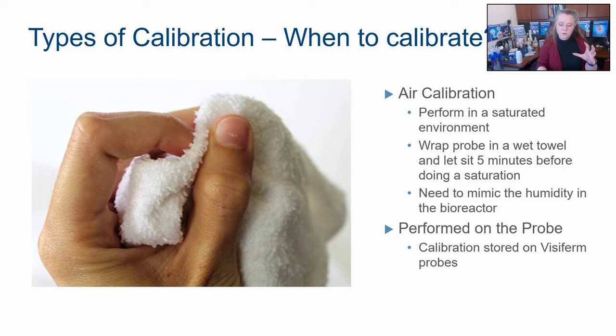It has to be a certain volume of cloth, because what happens in a wet towel? It evaporates. Evaporation does what? Temperature change. So if you just did a thin amount of paper towel, it's going to evaporate so fast, it's going to be very temperature unstable. A big rag, super simple, nice and wet, gives you that humid environment that mimics the bioreactor. Really simple. It writes it to the probe. Now we've calibrated the sensor.